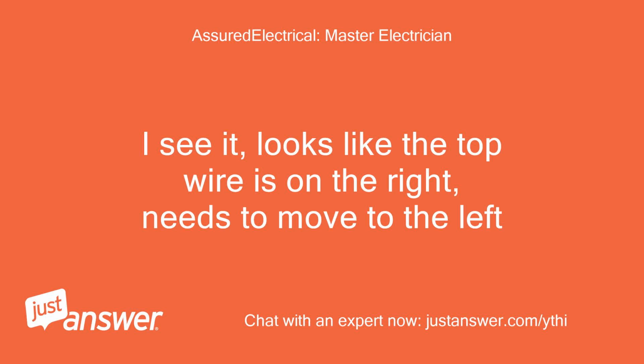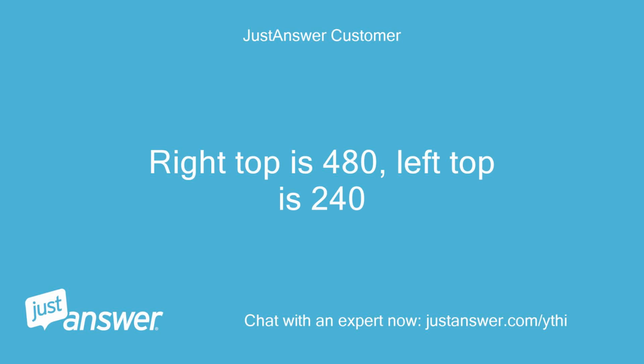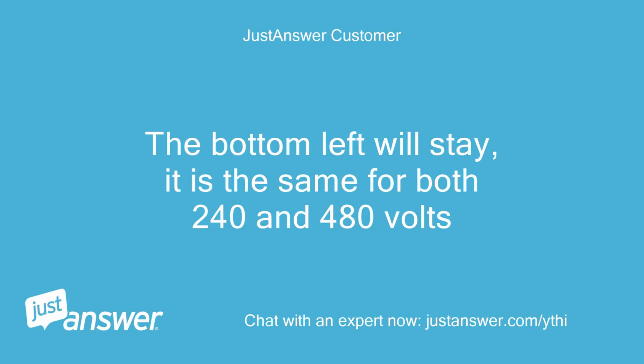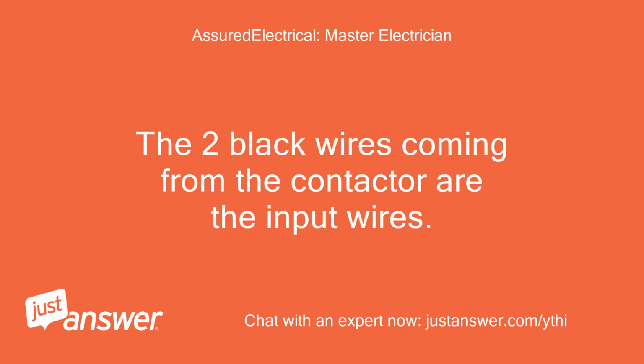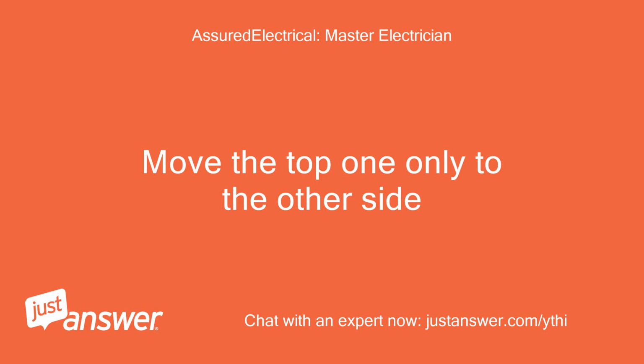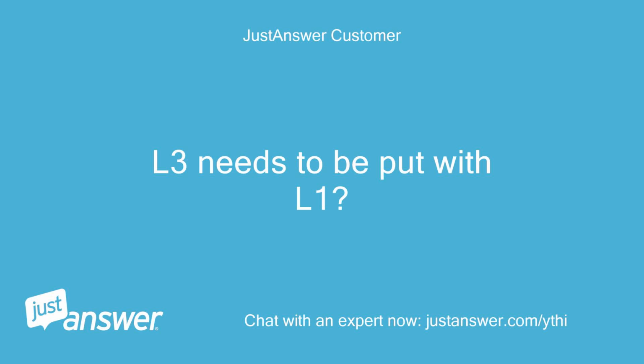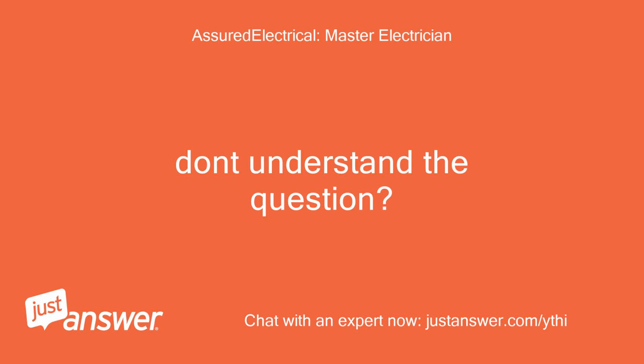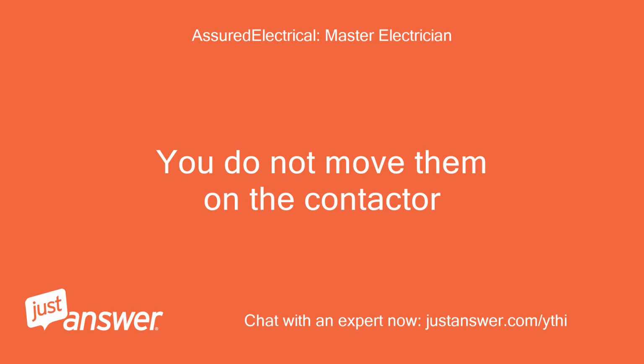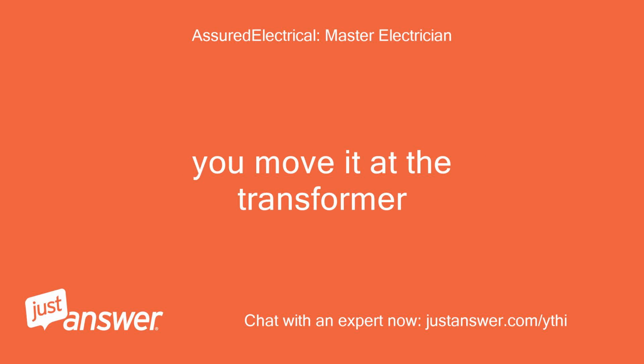I see it, looks like the top wire is on the right, needs to move to the left. Right top is 480, left top is 240. The bottom left will stay, it is the same for both 240 and 480 volts. The 2 black wires coming from the contactor are the input wires. Move the top one only to the other side. L3 needs to be put with L1. Don't understand the question? You do not move them on the contactor. You move it at the transformer.